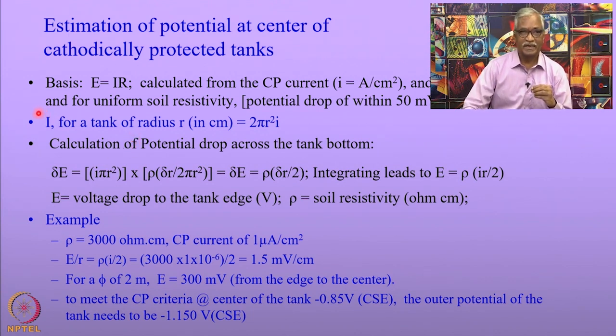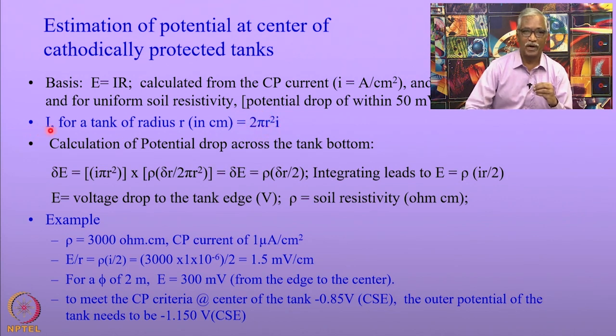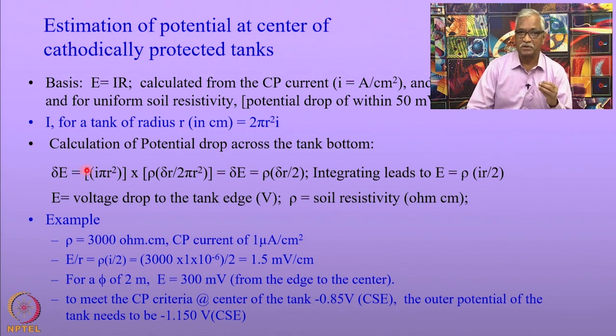First, calculate the current required for cathodic protection — this is done by knowing the current density and the area of the tank, so the total current required for protecting the tank can be calculated.